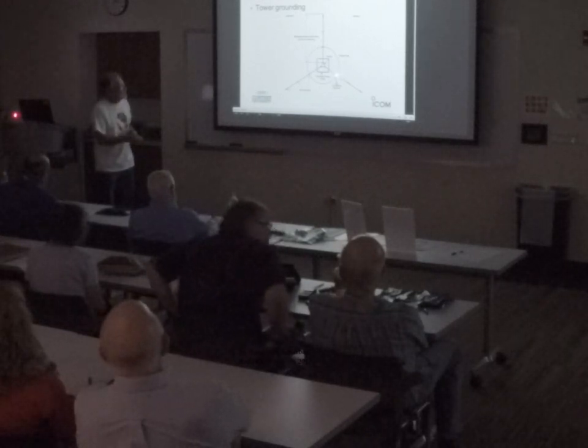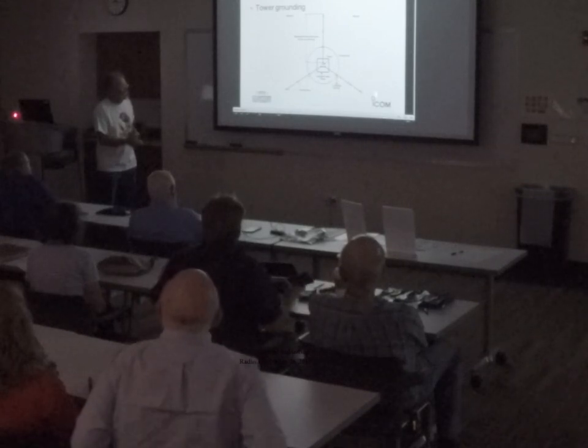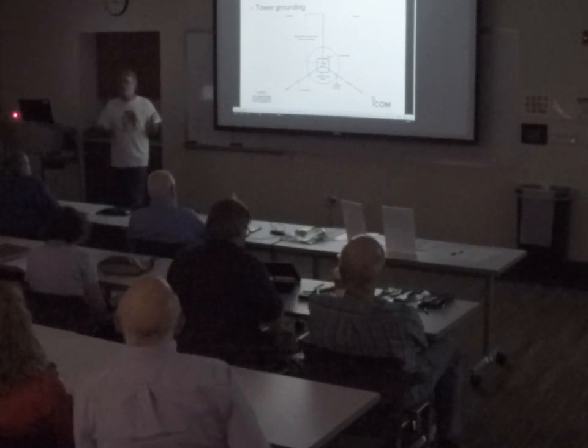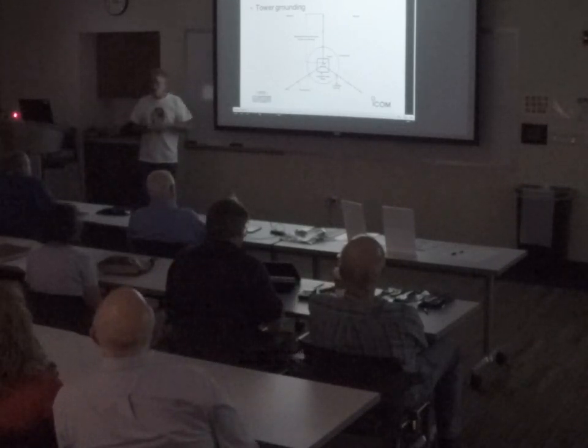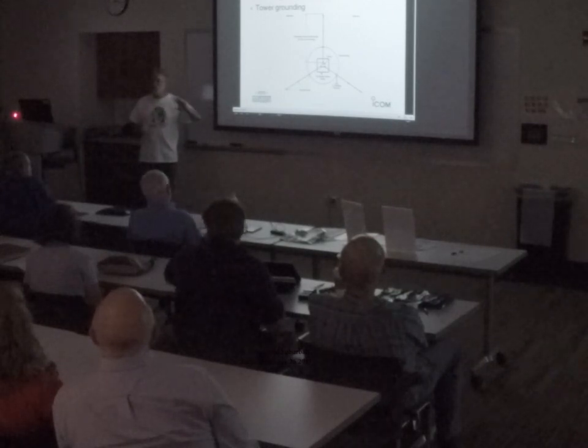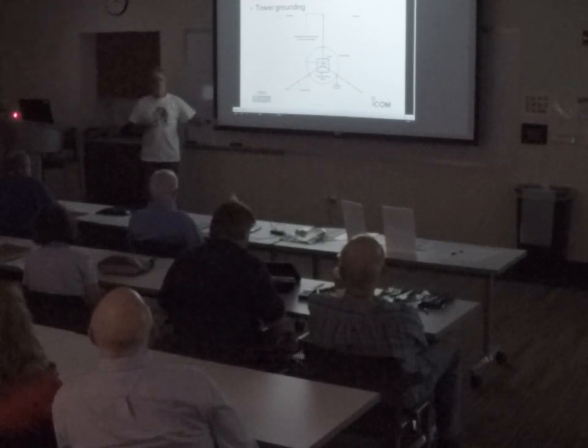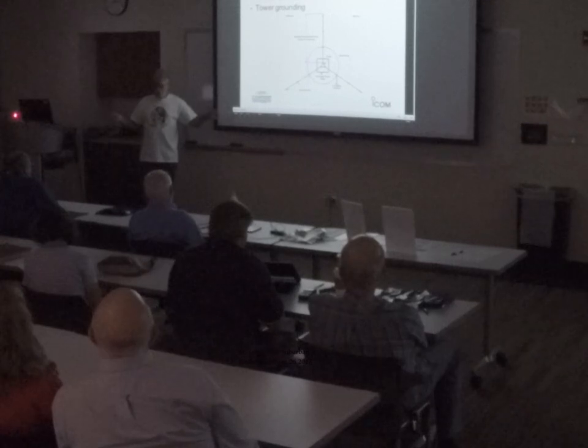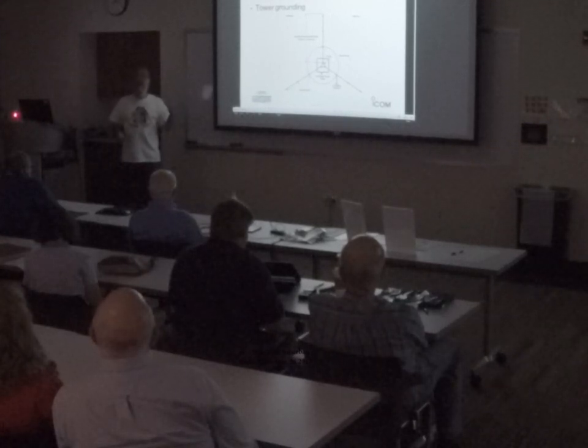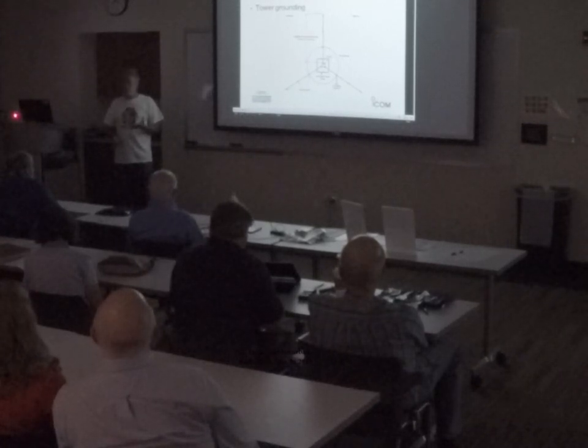There should be a connection to your station ground if you're anywhere from 50 to 200 feet from the house. Once you get beyond 200 feet or so, the inductance of that connection is too great to be very effective. It's only useful at AC safety frequencies.